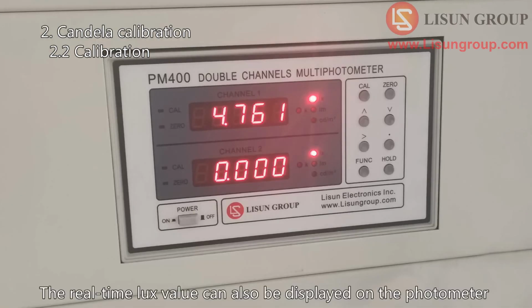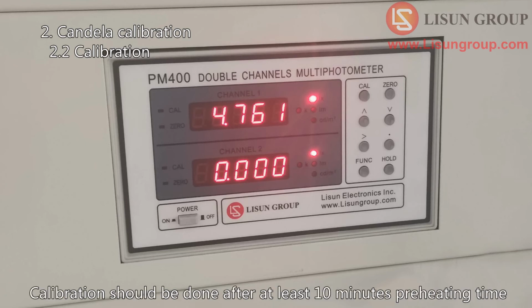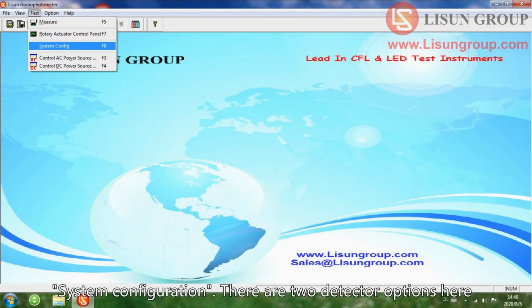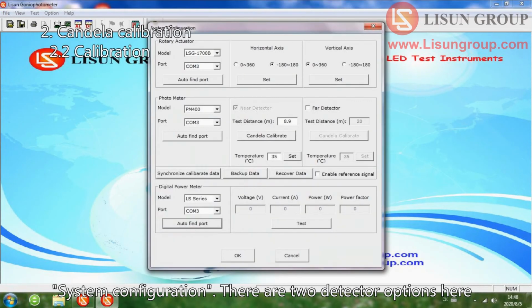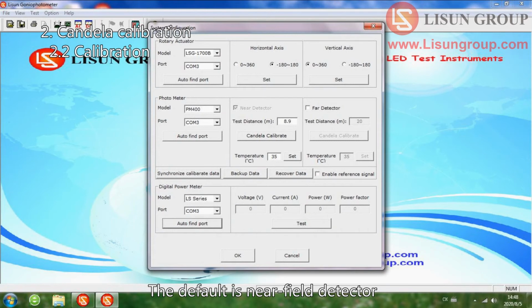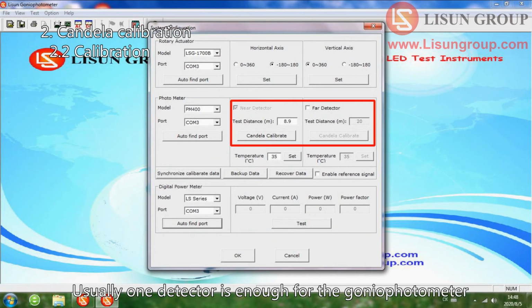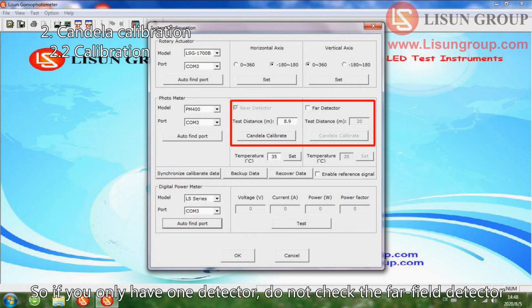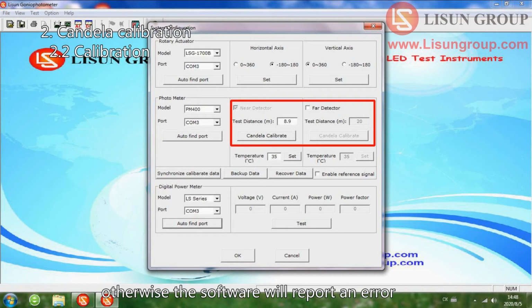The real-time lux value can also be displayed on the photometer. Calibration should be done after at least 10 minutes preheating time. System configuration. There are two detector options here. The default is near-field detector. Usually one detector is enough for the goniophotometer. So if you only have one detector, do not check the far-field detector, otherwise the software will report an error.